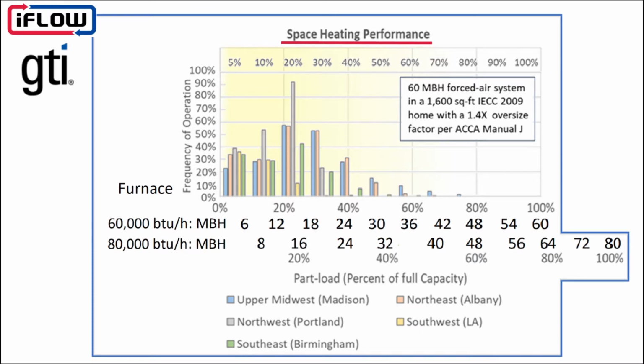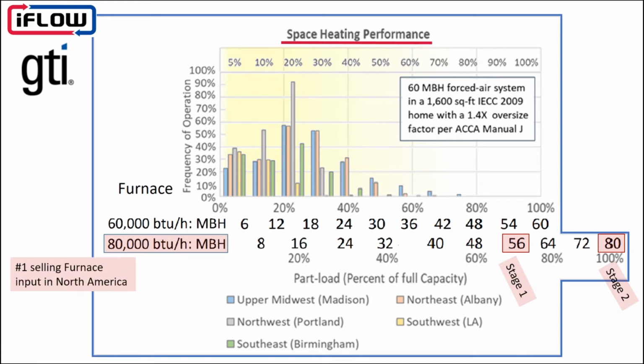We're going to start by looking at an 80,000 BTU furnace. Why an 80,000 BTU furnace? It's because it's the number one selling input in North America. So we install this 80,000 BTU 2-stage furnace. In stage 1, the unit will come on at about 56,000 BTUs, well over twice the 24,000 BTUs that we actually need. And when it goes up into stage 2, it'll ramp up to 80,000 BTUs, well over 4 times what we need in terms of actual delivery in the home. If we need 20,000 BTUs and we're delivering 80,000 BTUs, we're delivering almost 4 times the amount of heat that the home needs.